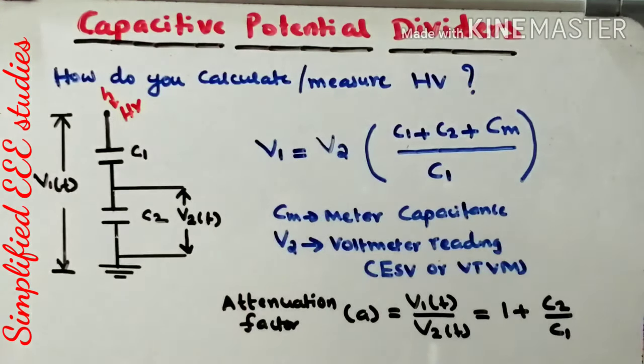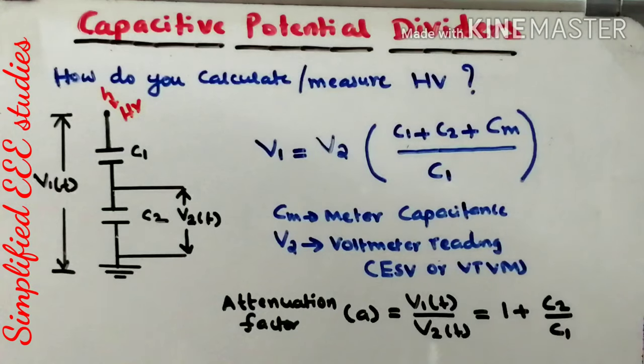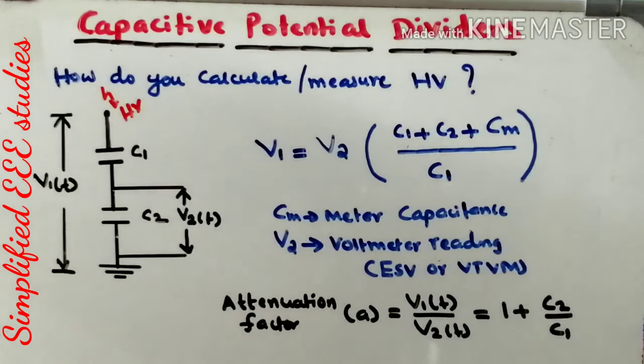Usually, this kind of voltage will be either fast rising voltage, impulse voltage, or high pulses. This can be easily measured with the help of Capacitive Potential Divider. While designing, one important factor is the attenuation factor, which plays the most important role. The attenuation factor is the ratio of V1 divided by V2, which equals 1 + C2/C1. Knowing the values of C1 and C2, you can easily calculate the attenuation factor. This is the way to calculate the total voltage externally using Capacitive Potential Divider.